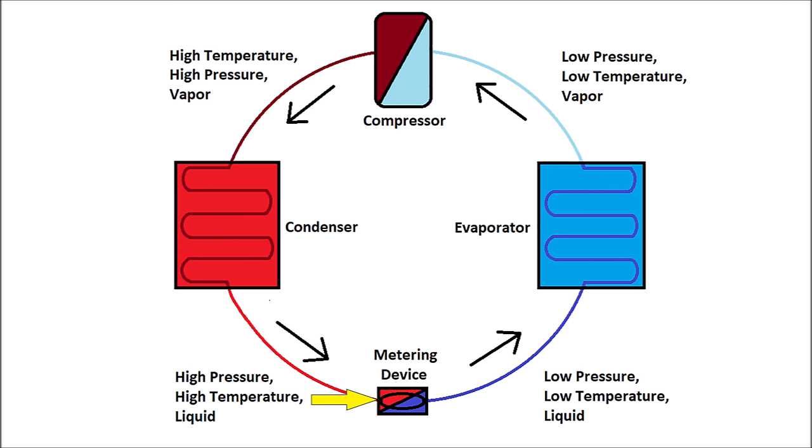The high pressure, high temperature liquid refrigerant enters the metering device, and then it exits the metering device as a low pressure, low temperature liquid. This is due to the very small opening within the metering device that lowers the pressure of the refrigerant.